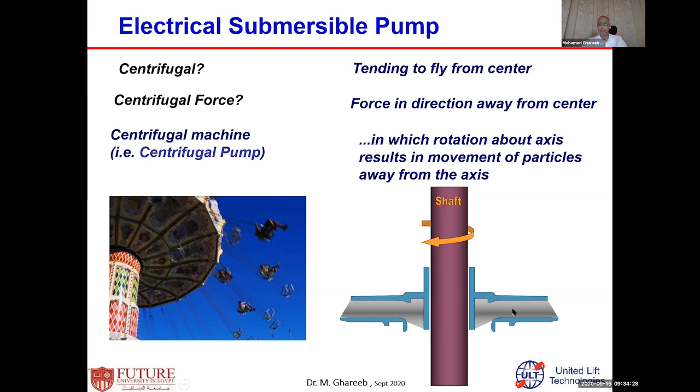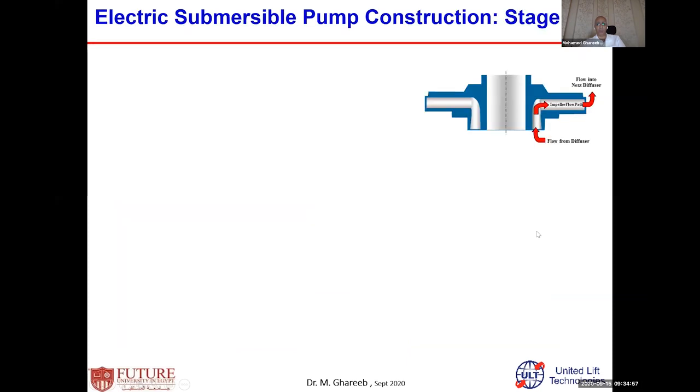This is a pump shaft, and this is the impellers of the pump shaft. When the pump shaft is rotated, the impeller is rotated. If there is a fluid coming from the bottom of the impeller, and this is rotating the impellers, they take the fluid and send it out with centrifugal force based on the velocity, and based on a lot of different factors affecting the centrifugal force. Then the fluid comes from one area, from the bottom of the centrifugal, goes out of the impeller, through what you call the diffuser, with a certain force.